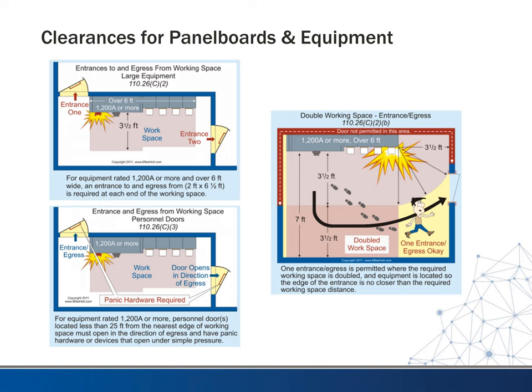So last thing I just want to touch on here is if you're dealing with switchboards, then you fall into a little bit different category. What we're looking at here is anything that's rated 1200 amps or more. That would usually be a switchboard, the smallest switchboard you could get. You can get panel boards sometimes that large, but this usually comes into play in main electrical rooms with the switchboard. And if the gear lineup is 6 feet or more in width, according to the code, 110.26(C)(2), we have to have two entrances if we want to maintain just the original workspace, okay?